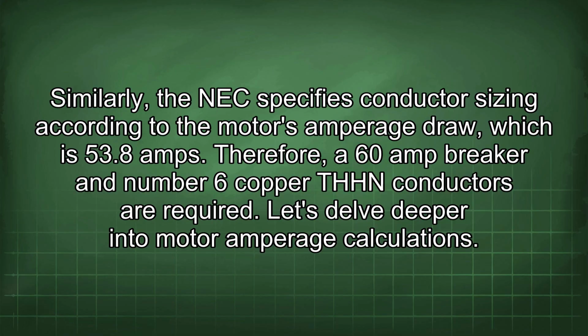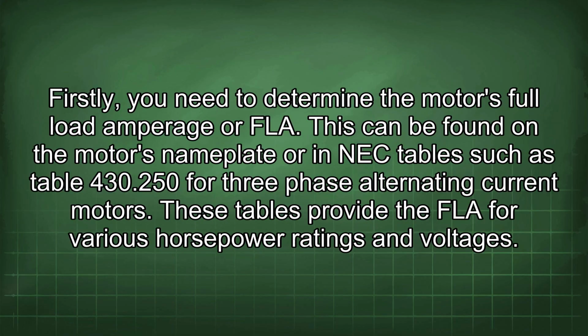Let's delve deeper into motor amperage calculations. Firstly, you need to determine the motor's full load amperage or FLA. This can be found on the motor's nameplate or in NEC tables such as Table 430.250 for 3-phase alternating current motors. These tables provide the FLA for various horsepower ratings and voltages.